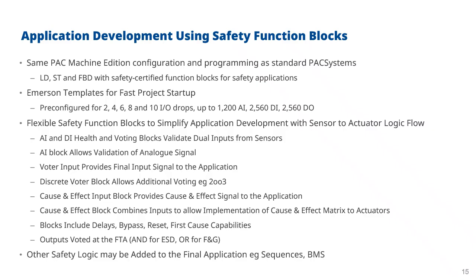So we've got templates pre-configured for 2, 4, 6, 8 and 10 I/O drops, and they're configured with capabilities of up to 1200 AI, 2560 DI and 2560 DO. So we feel that would cover us for the vast majority of applications. Potentially we could go for more than that in future versions, but more likely users aren't going to put all their eggs in one basket, as we say. More likely it would be preferable to have multiple safety systems and they will be able to communicate with each other in the future using that black channel communications.